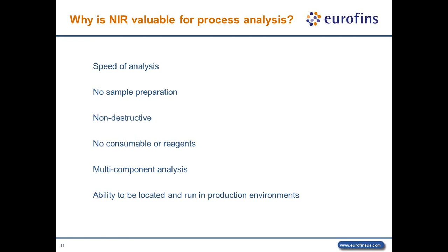So why is inline NIR valuable? In addition, NIR analysis is capable of utilizing fiber optic probes that can be installed in a variety of locations throughout the plant. NIR fiber optic probes come in a variety of configurations and are rugged enough to endure high temperature, high pressure environments. This makes it possible to achieve true real-time analysis of inline material without the need to pull samples. This can help to reduce operator exposure in potentially hazardous environments and potential changes to a volatile material from the time the sample is pulled to when it is tested.